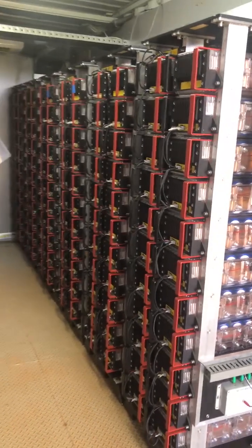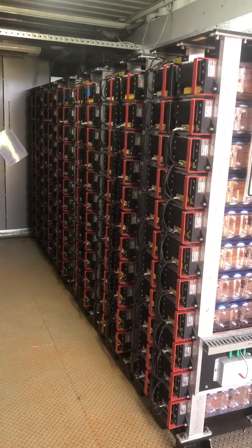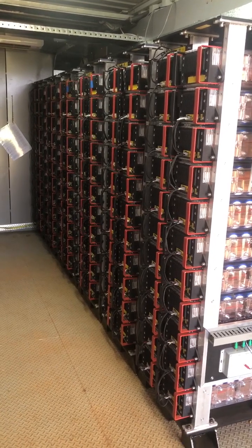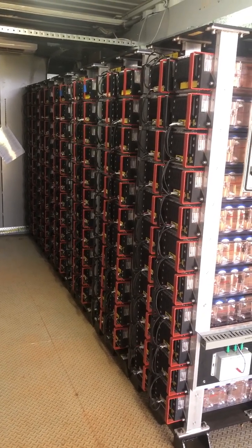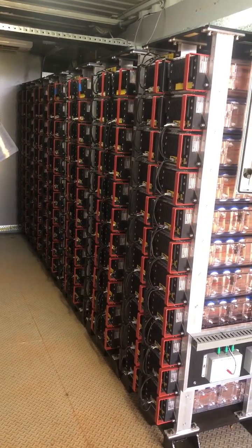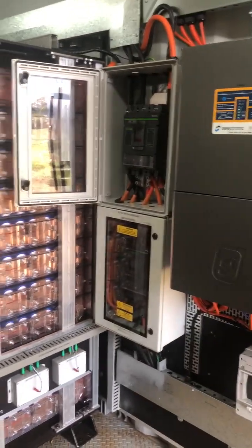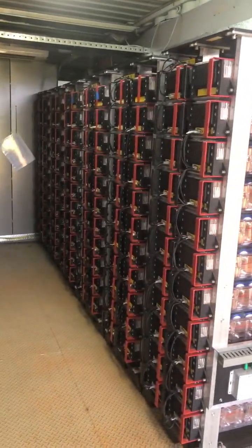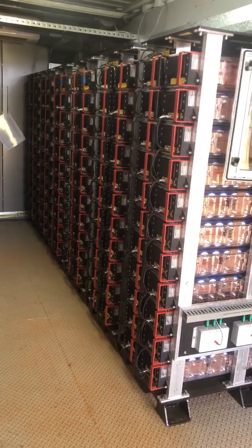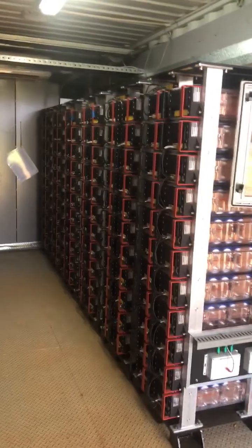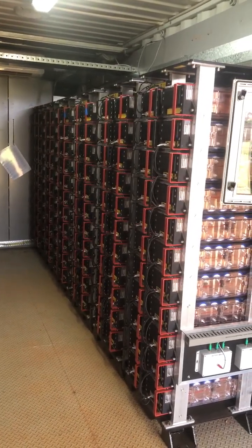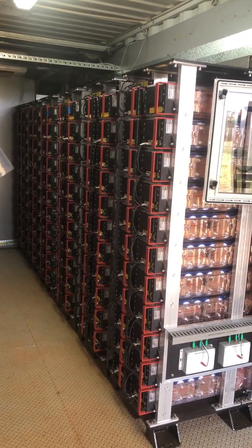And when I say battery stack, these are the batteries. So there's actually 6 battery stacks here, meaning that there are 3 battery stacks for each string. So each battery stack is rated at 48 volts, and when we put 3 of them in series, we end up with about 160 volts, which is what this system is designed to operate at.